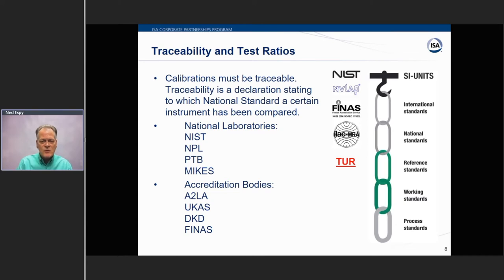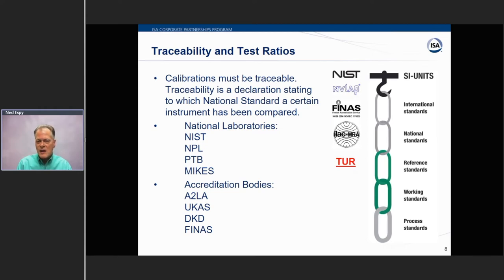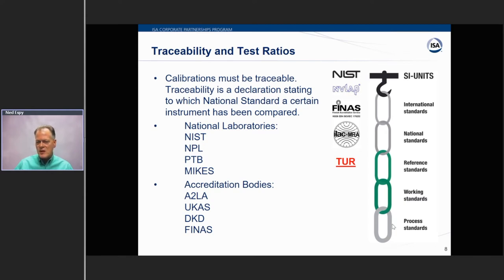When talking about making measurements, we want to use good practices with our equipment and show traceability — your pedigree back to national standards. In the United States, NIST is very familiar, and NVLAP is their accrediting arm. BMX uses FINAS for our accreditation, recognized worldwide through a mutual agreement. Here at BMX, we have reference standards and we deliver working standards. One goal is to maintain a 10-to-1 ratio in the lab — standards that are 10 times more accurate than the calibration equipment being certified. This is the test uncertainty ratio (TUR).